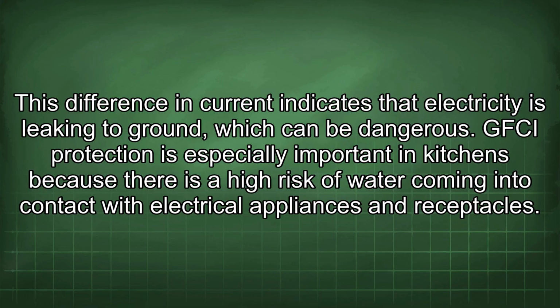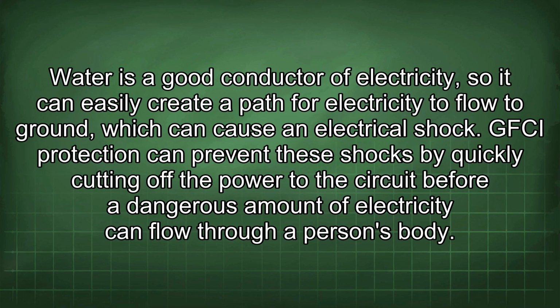GFCI protection is especially important in kitchens because there is a high risk of water coming into contact with electrical appliances and receptacles. Water is a good conductor of electricity, so it can easily create a path for electricity to flow to ground, which can cause an electrical shock. GFCI protection can prevent these shocks by quickly cutting off the power to the circuit before a dangerous amount of electricity can flow through a person's body.